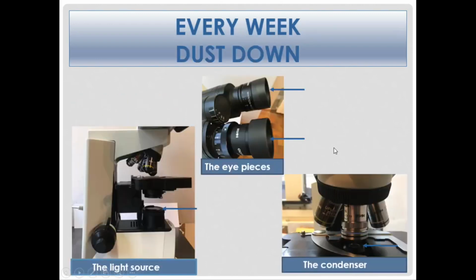When I talk about removing dust from the microscope, what are the most important areas to clean? The light source here, and the lens here. If you have a filter or a removable lens, don't hesitate to remove it to clean it thoroughly. The condenser here.